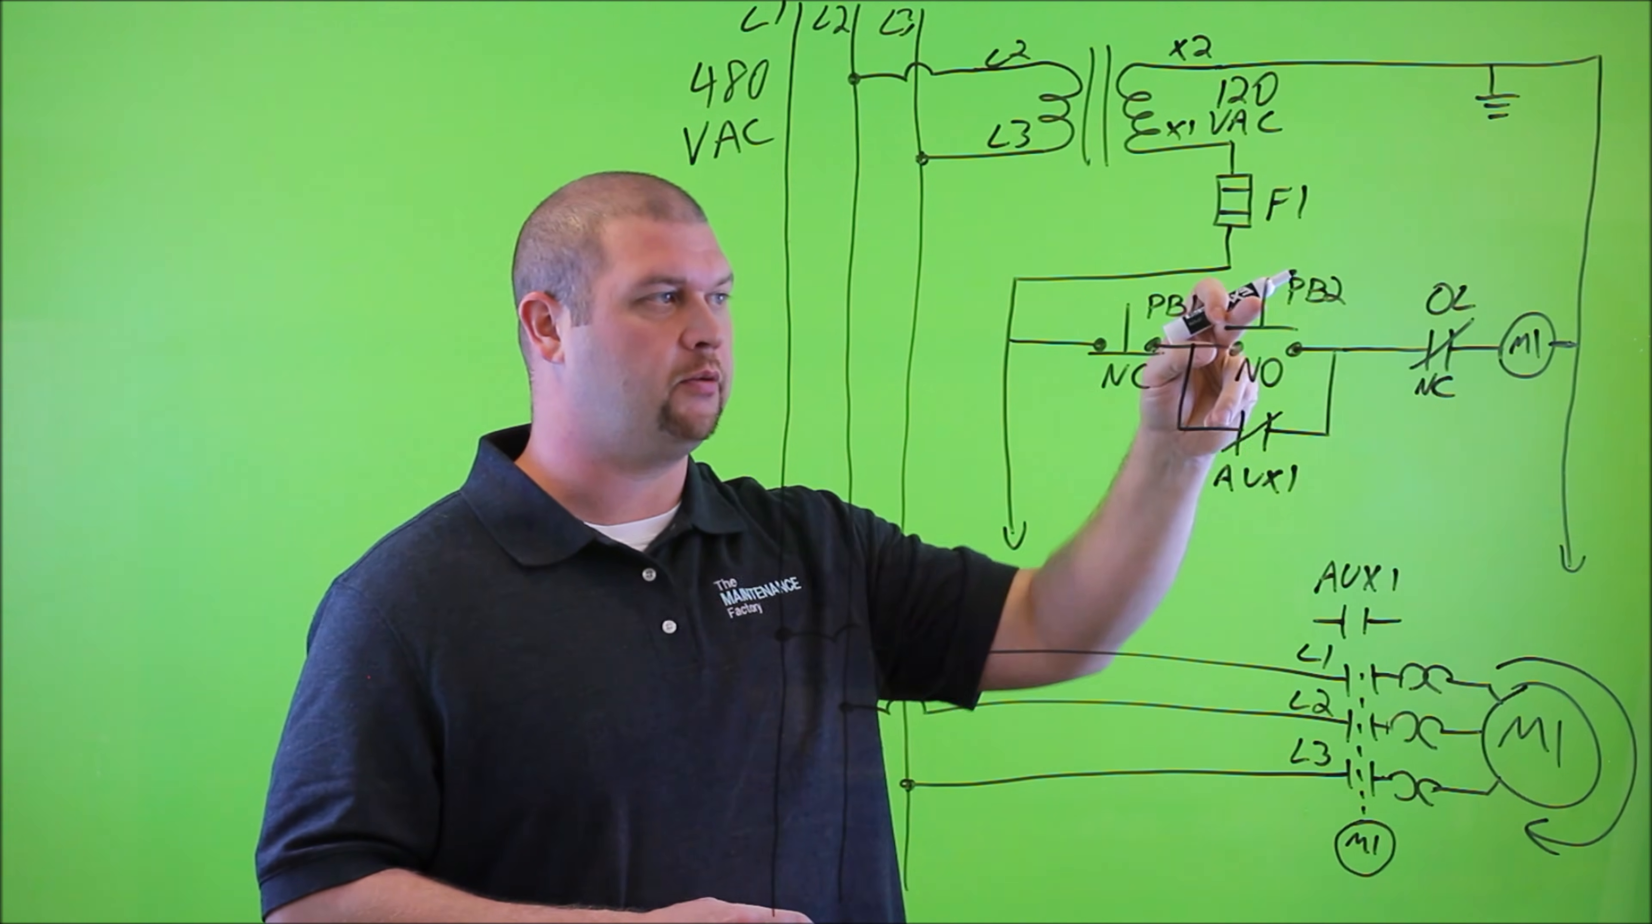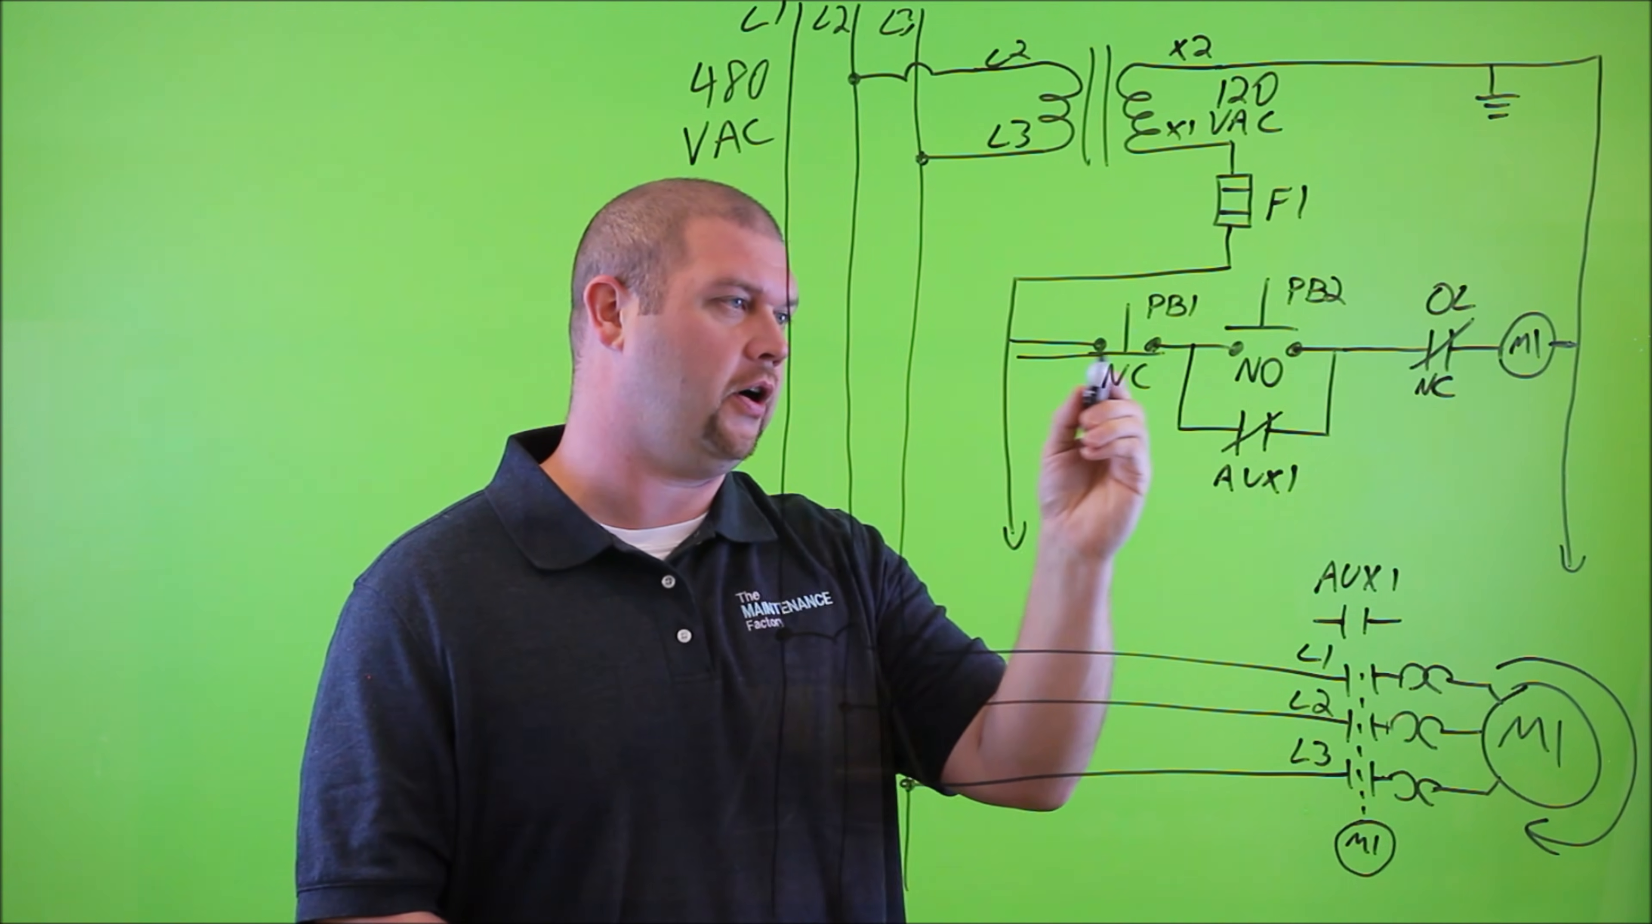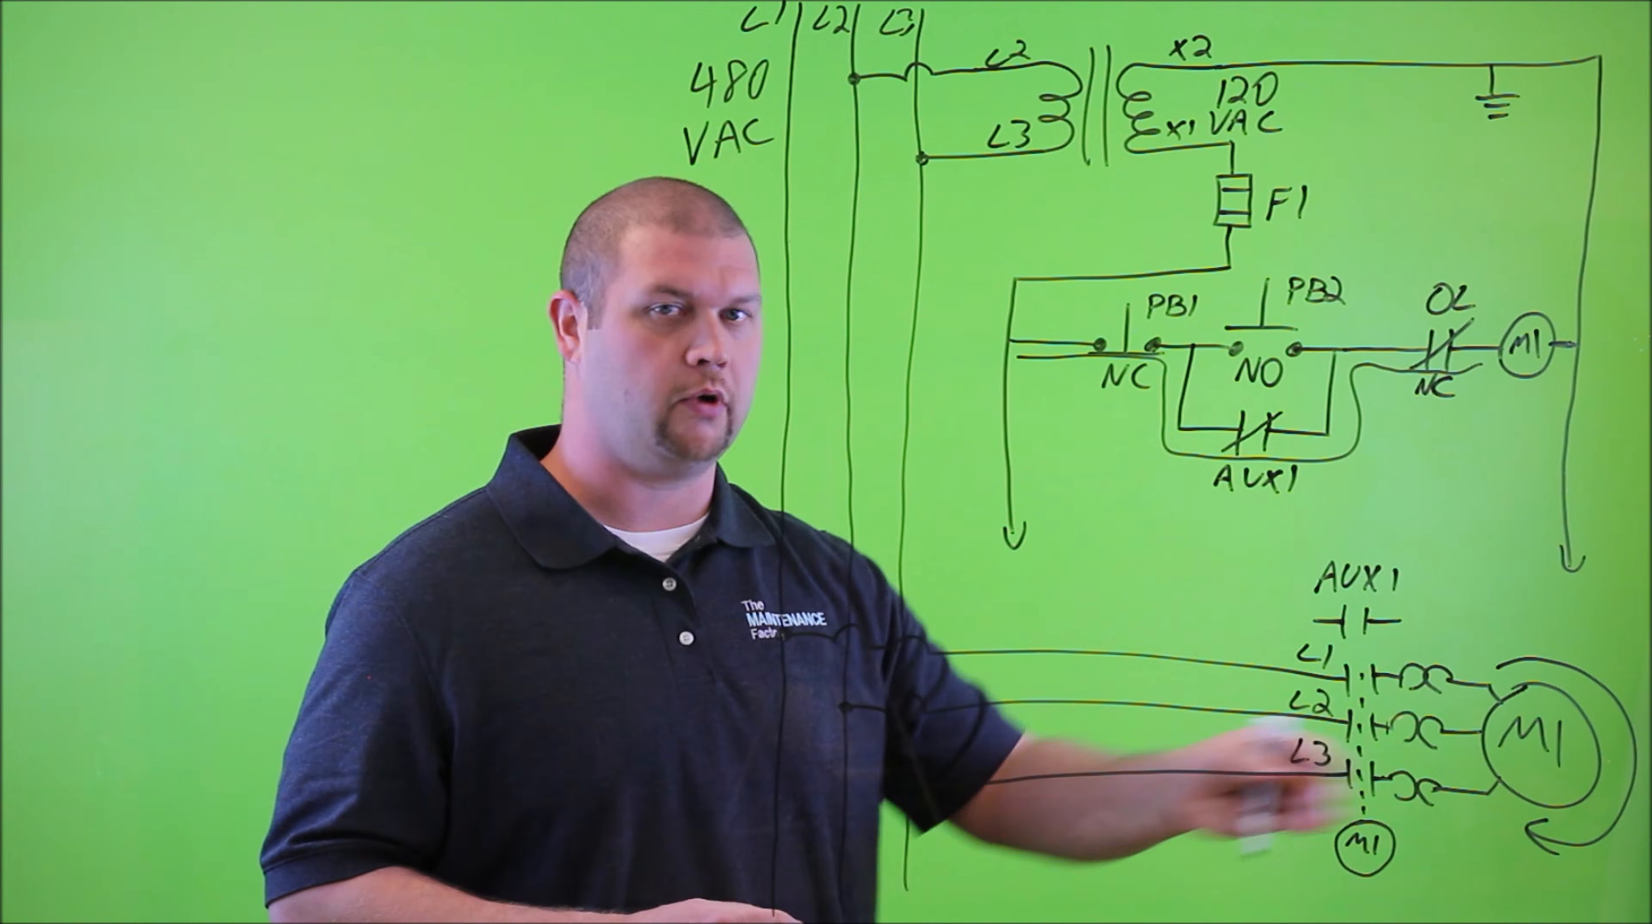And now, as we release the start button, this auxiliary contact provides that path for current to flow. So now, current is going to flow in this direction to the coil, keeping the coil energized, therefore keeping the contactor closed, and continuing to rotate the motor.